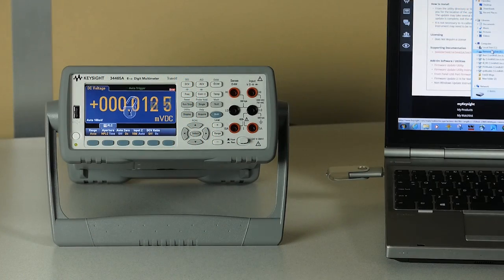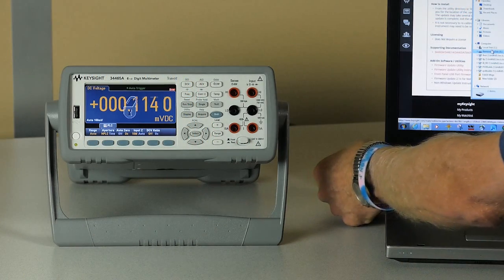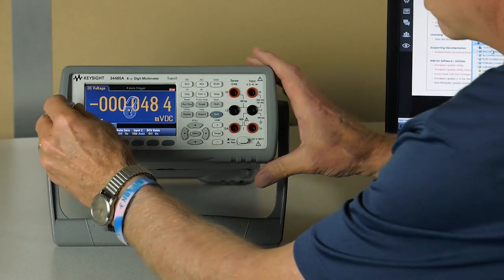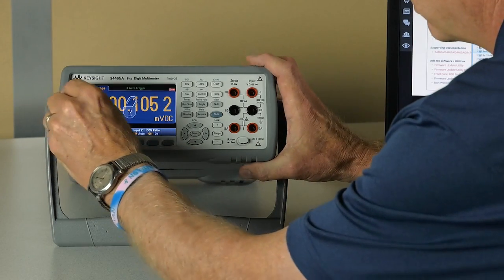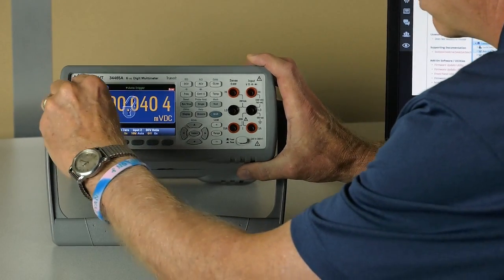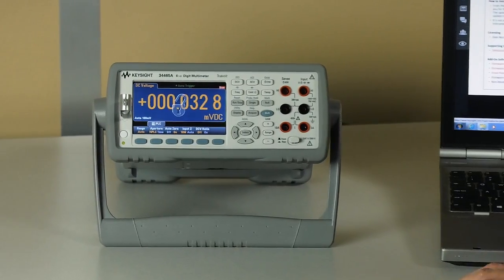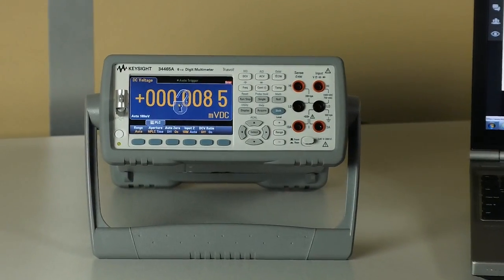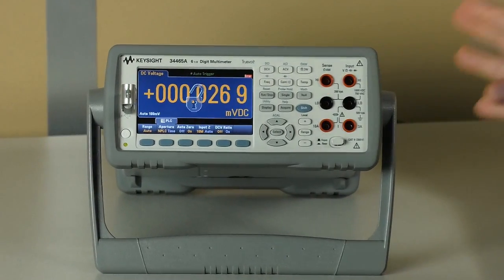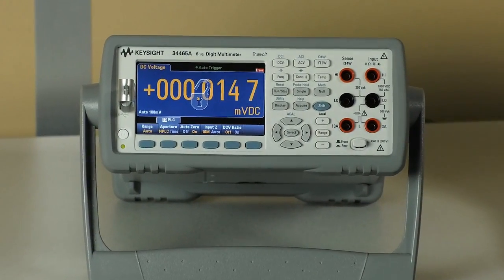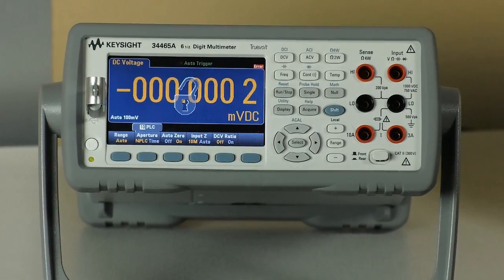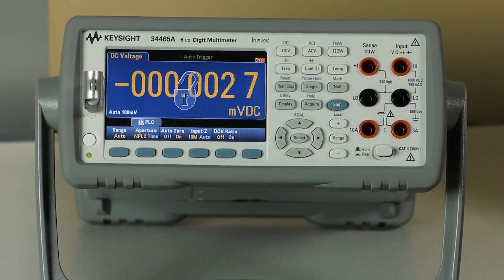So at this point, what I will do is I will remove the thumb drive from the PC and insert it into the instrument. So once the USB file is transferred from the PC to the instrument, we'll go ahead and begin the download from the front panel.